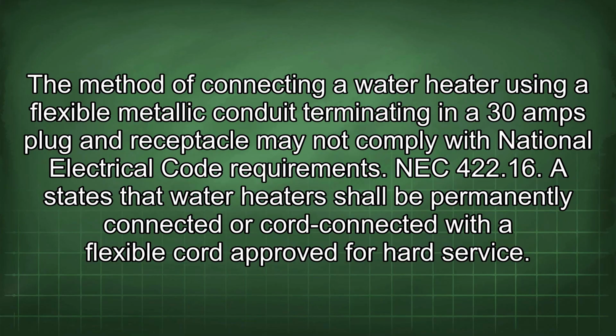The method of connecting a water heater using a flexible metallic conduit terminating in a 30 amps plug and receptacle may not comply with National Electrical Code requirements. NEC 422.16 states that water heaters shall be permanently connected or cord connected with a flexible cord approved for hard service.